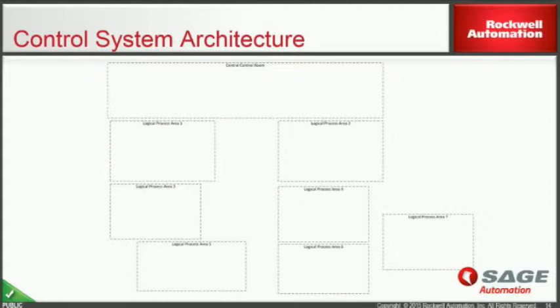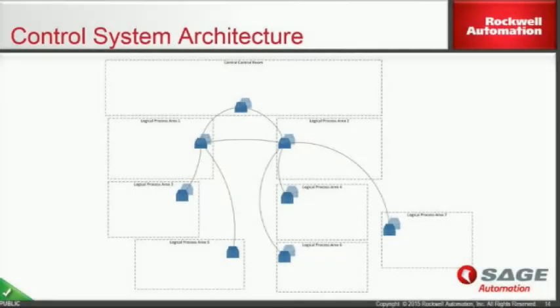facility. And they were connected by, so these 3 stacks here were the 3750 Ciscos, providing the distribution layer connectivity. And down in the process buildings, we had Stratix, either single or redundant Stratix managed switches in a star topology, but redundant star topology. Our restriction here was being a brownfield site. We had to maintain and utilise existing conduits around the facility. If it was a brand new site, we probably would have had a self-healing ring or a number of self-healing rings.